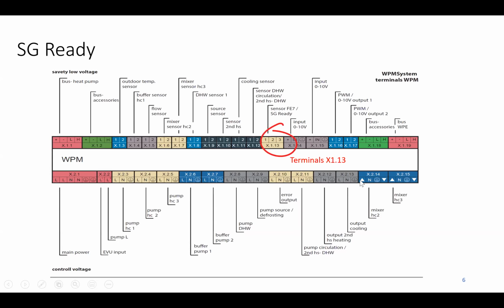Okay, let's just talk heating for a moment. If we just have a heating system, we can, if we so wish, set up those circuits running purely on the heat curve. Now, I'll go into heat curves and so on in another module. But what that means is we're using the ambient sensor, which we put into X1.3, and we're making a determination based on the temperature outside of how hot to run these circuits, okay?